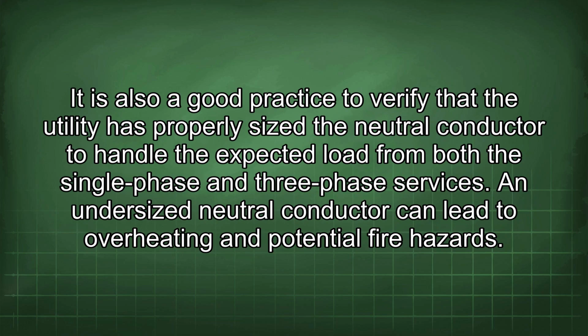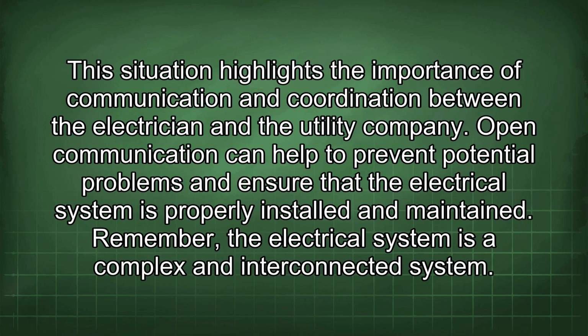It is also a good practice to verify that the utility has properly sized the neutral conductor to handle the expected load from both the single-phase and three-phase services. An undersized neutral conductor can lead to overheating and potential fire hazards. This situation highlights the importance of communication and coordination between the electrician and the utility company. Open communication can help to prevent potential problems and ensure that the electrical system is properly installed and maintained.